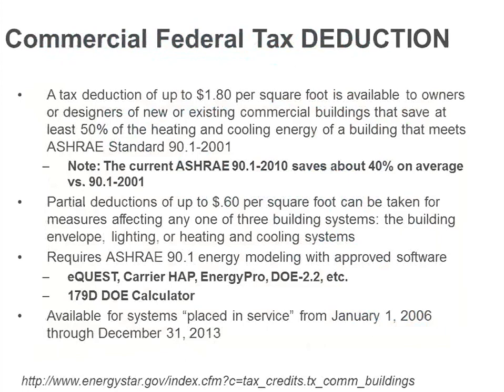There are commercial tax incentives available. It is not a tax credit. It's a tax deduction in this case. And it doesn't really apply very well to a replacement project because basically you have to save 50% energy over the old ASHRAE 90.1 2001 standard. And by the way, the 2010 standard is about 40% more efficient than the 2001 standard. So basically, if you get the building up to code today, you're almost there. But you've got to get the whole building up to code, not just one boiler or something like that.